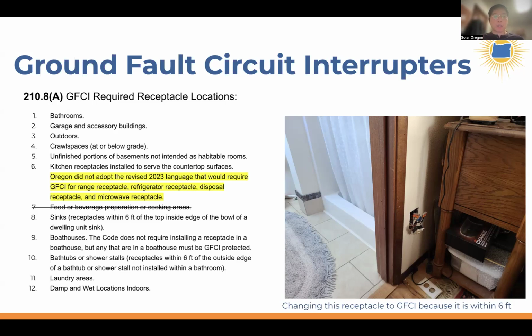Another update shown in this picture: receptacles within 6 feet of the outside edge of a bathtub or shower should not be installed within the bathroom, and if within 6 feet, it needs to be GFCI. In this picture, the receptacle is not within the bathroom, so it meets that requirement, but it is within 6 feet of the shower stall, so it's being changed out to GFCI. You can imagine where this requirement came from.